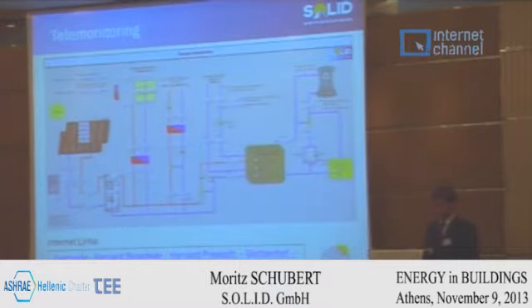So what we also do on all our solar cooling systems and also many of the other large systems is that we have a telemonitoring, because our experience is that such a solar thermal system needs regular intervals of checking the operation. So we can best from our office see the temperatures, if it still fits the demand. Also, during the first year, you have to look during different seasons, different climate, if the plant is still operating in the way it was supposed to. But of course, this doesn't replace the on-site maintenance, which also has to be done on all parts.